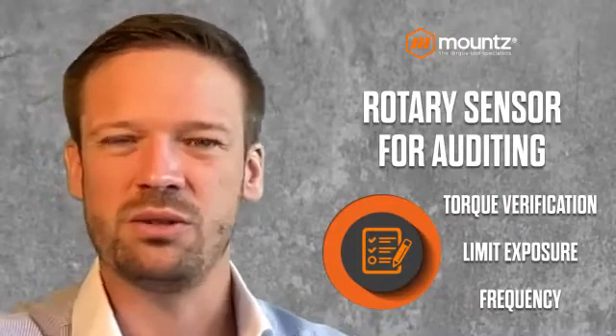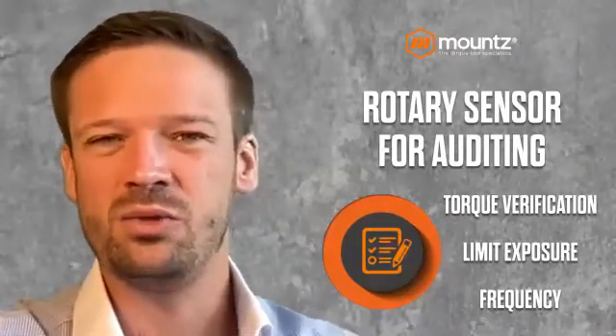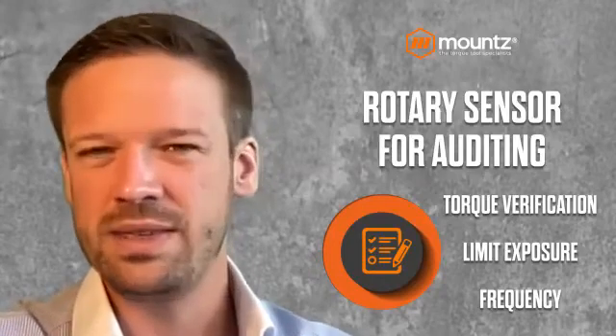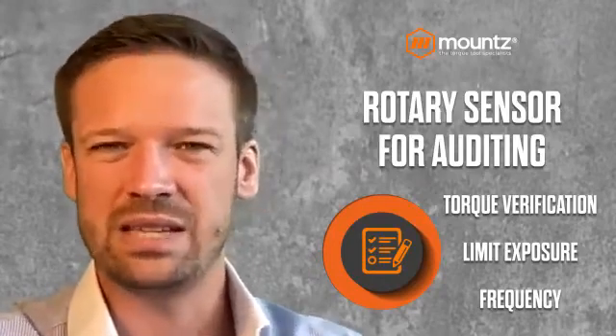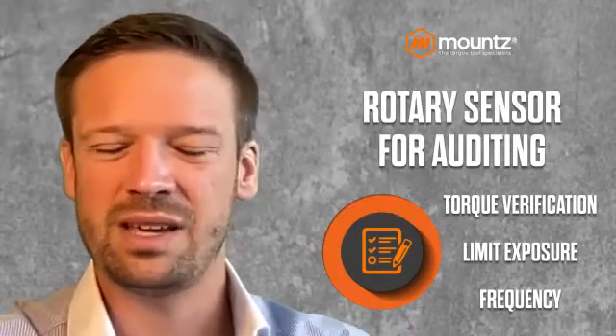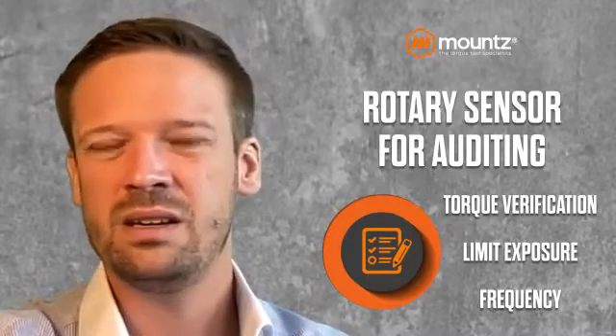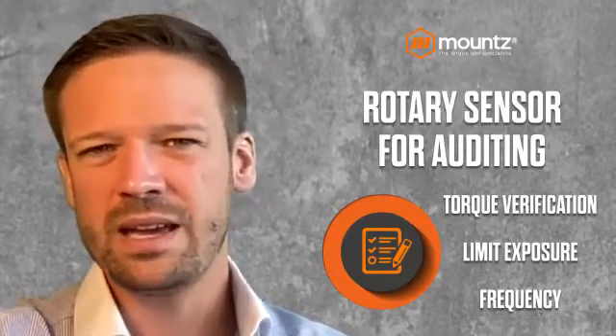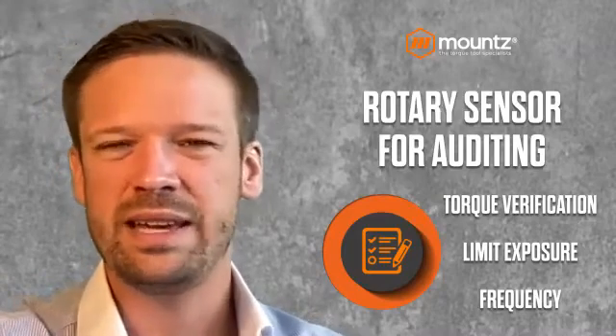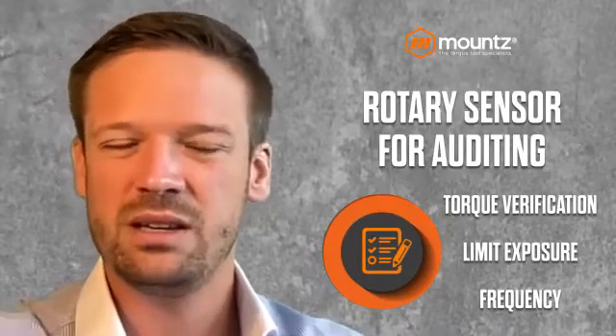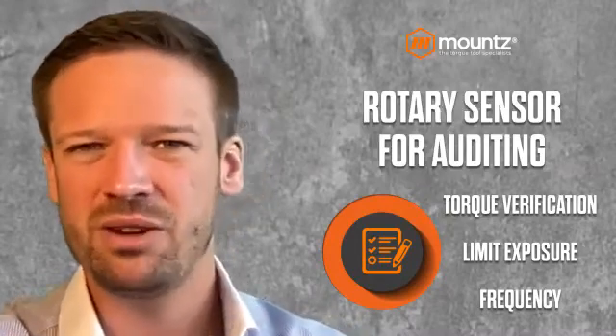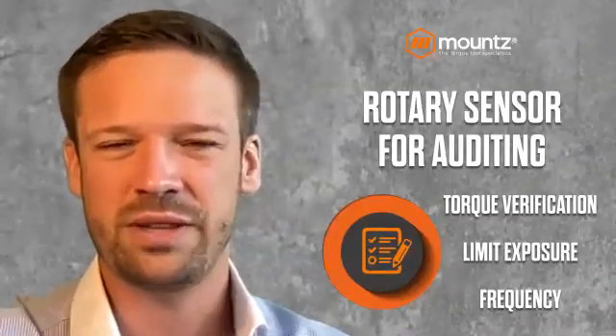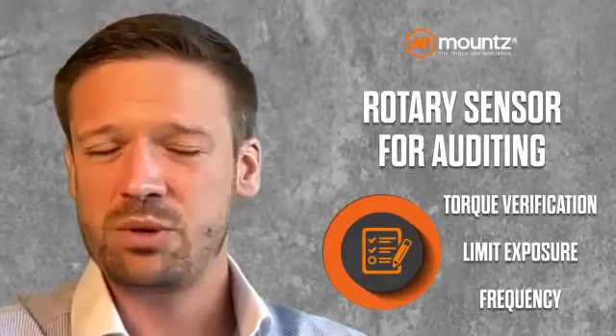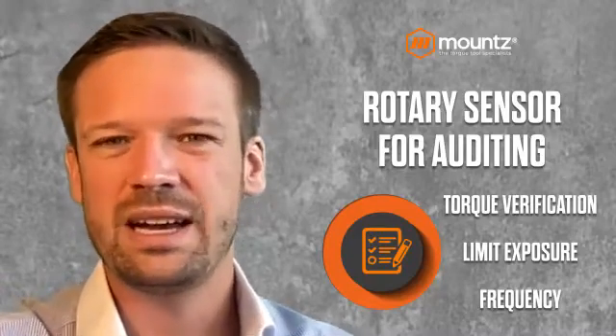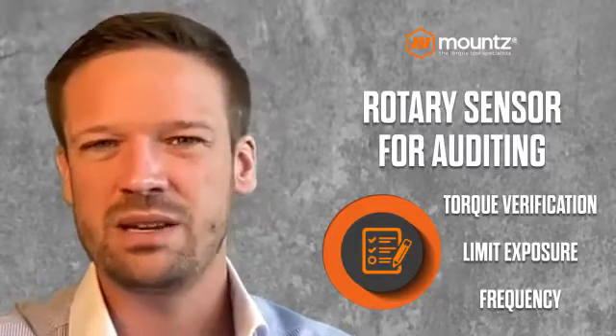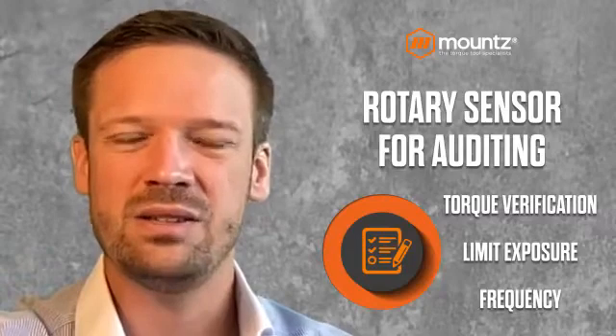What we do here is check the tool against production reality, most of the time during production. We collect the data and save it onto the torque analyzer, the network, and our computer. This helps limit exposure, as we can check if the tool matches requirements, and if not, take corrective actions. It limits exposure to quality issues, as the tool is regularly checked, making sure quality on the assembly line is properly respected.